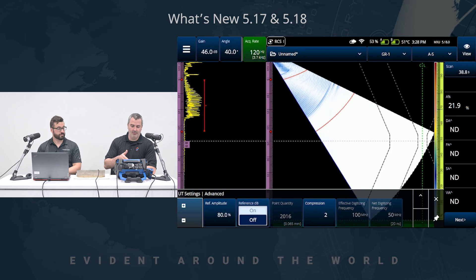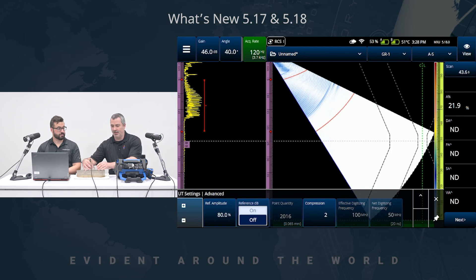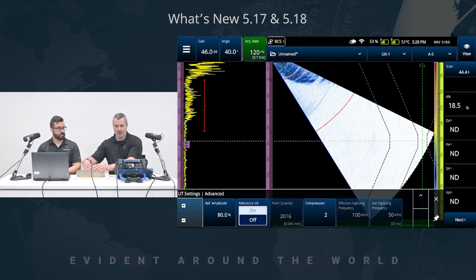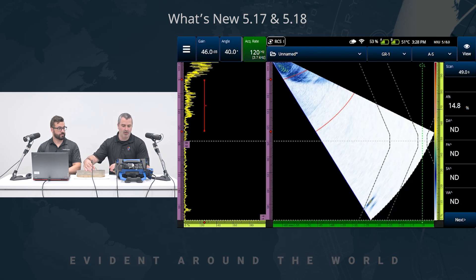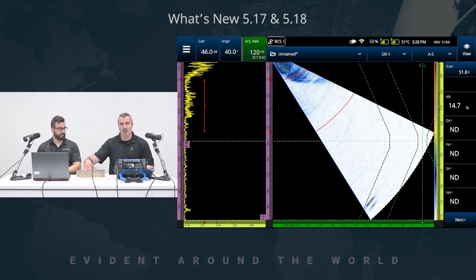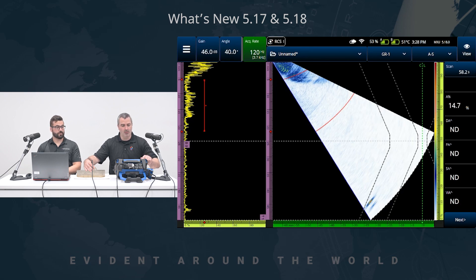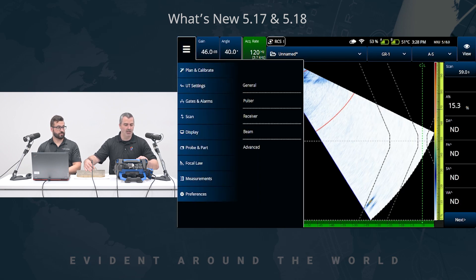So we have a compression factor of 2, net digitizing frequency of 50. If I look on the CAL block — let me get rid of the menu — the side drill hole is way down there. We don't have enough range. And eventually, we don't have enough range for the weld itself. So we want to change that.